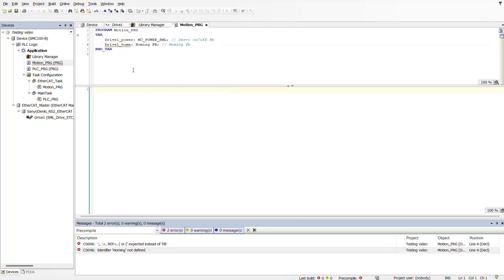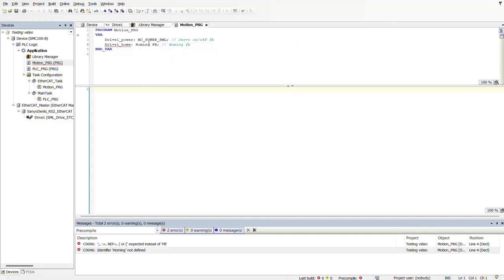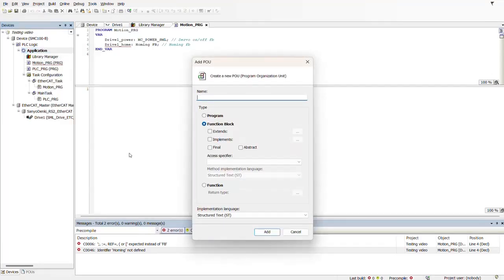However, like I mentioned before, we have our variable and then we have our function block. This function block is from my existing library, but I'm also going to create a POU — a function block for this specific homing block. We're going to do this by clicking on Application, Add an Object, then POU. Right here we're going to name it — I want to name this POU as HomingFB. With this function block we're going to be able to call it from our program as many times as needed.